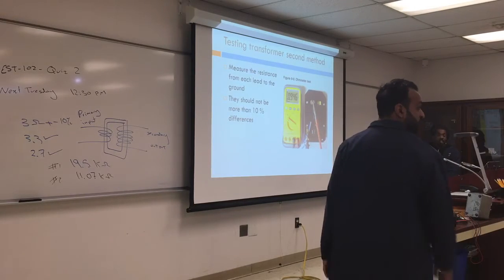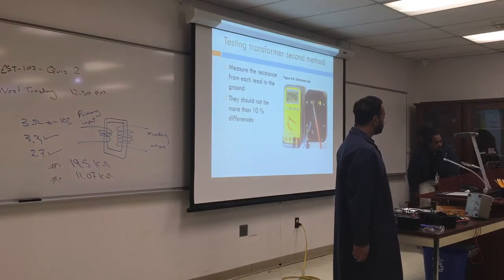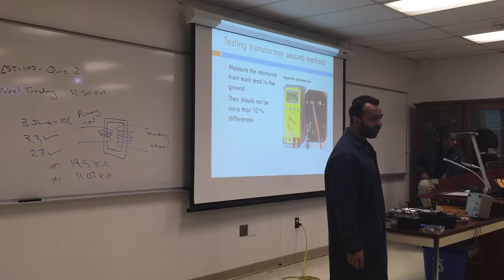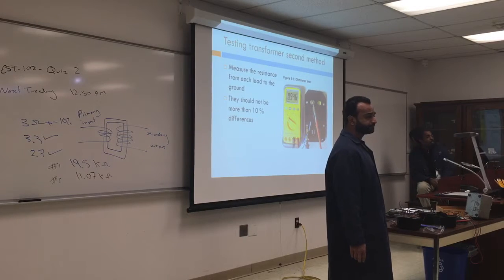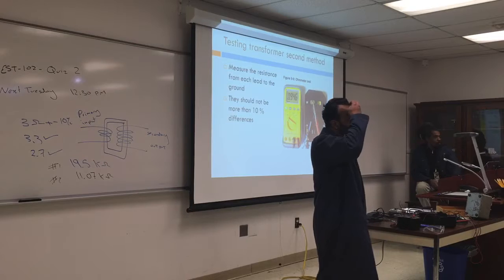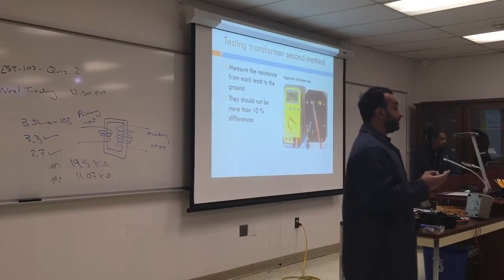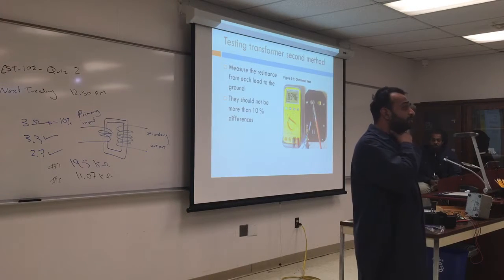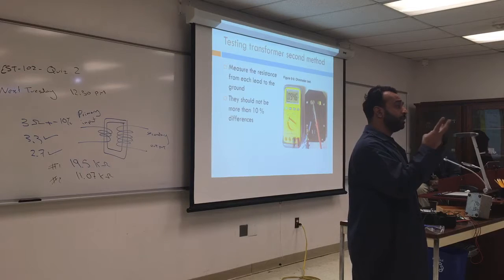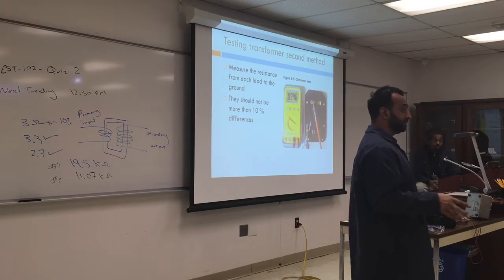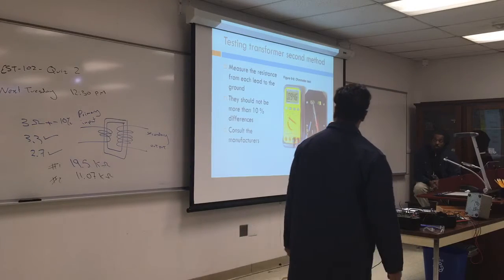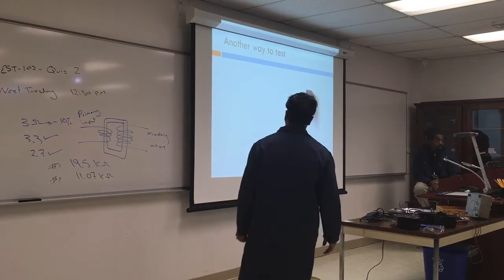You should check yourself, even if you ask them and they tell you they only did it once or twice. They'll tell you that they pressed the button, right in front of you. That's why the new primary control will allow you 3 resets, then it goes into hard lockout, which means you cannot reset anymore. Something is really wrong, consult the manufacturer.